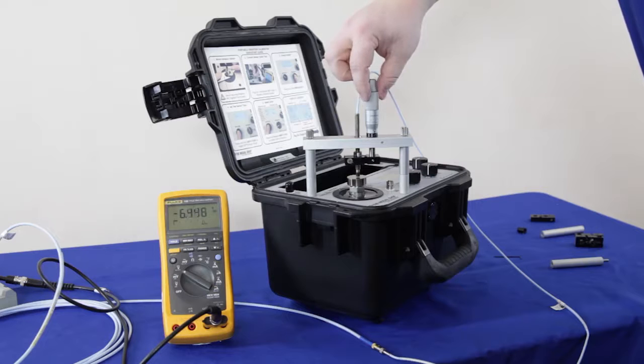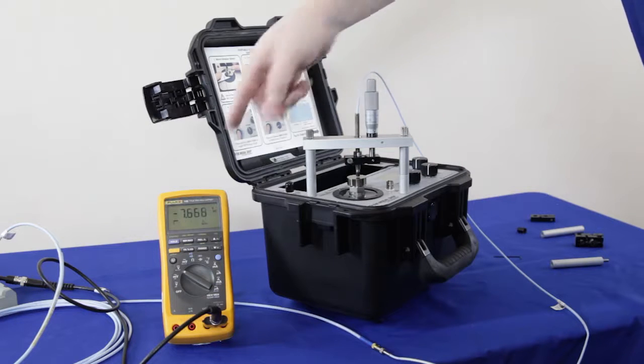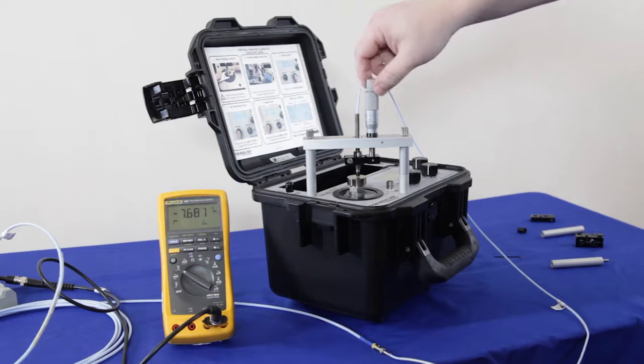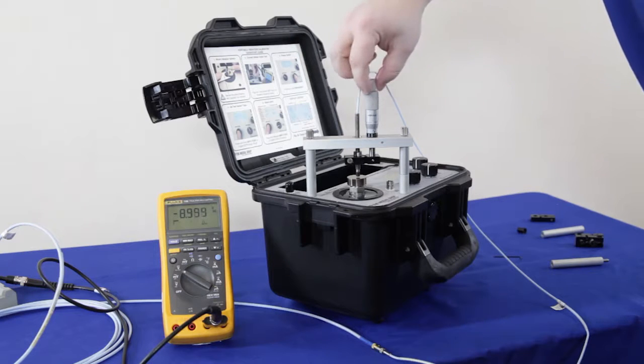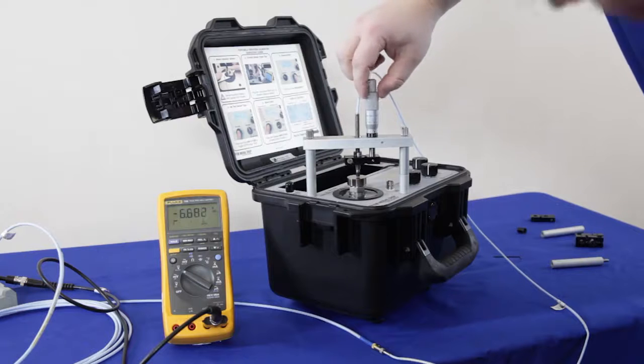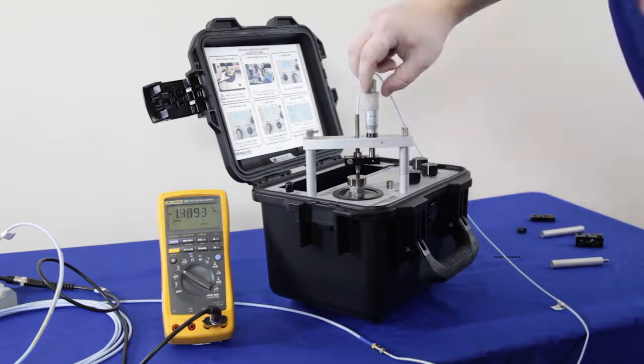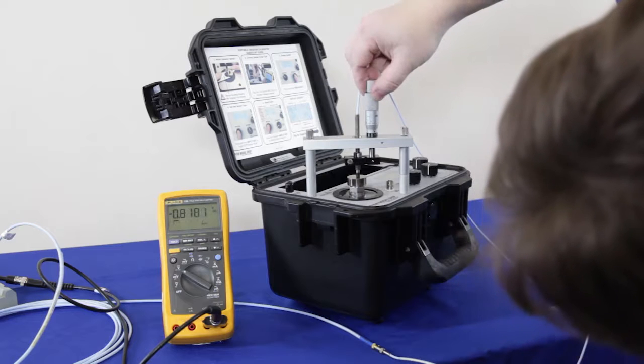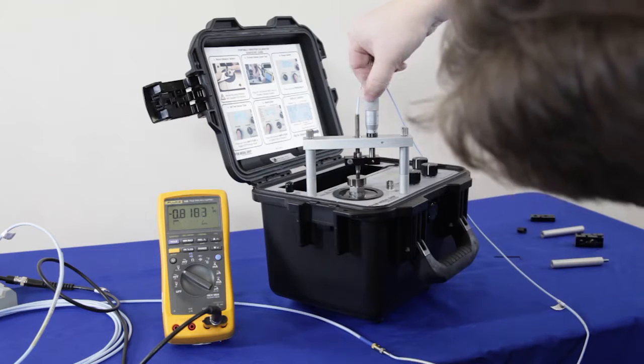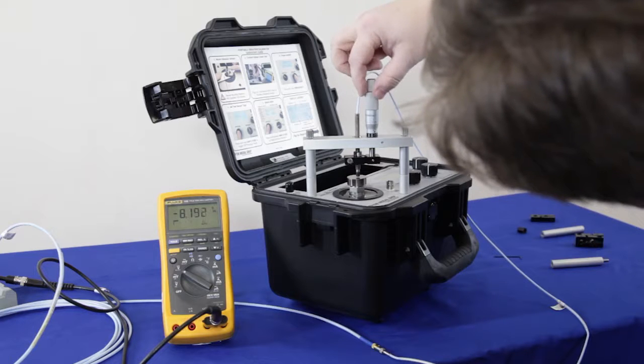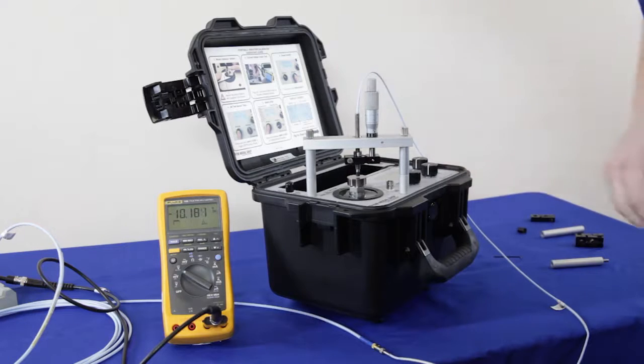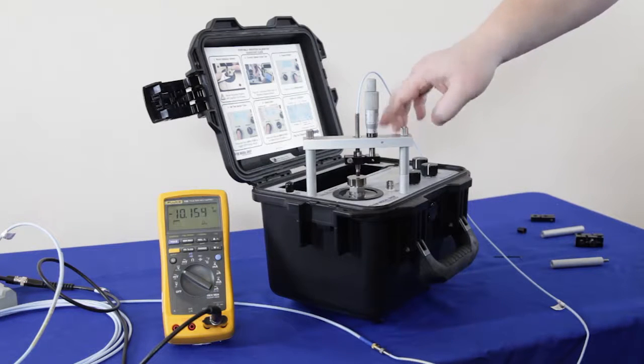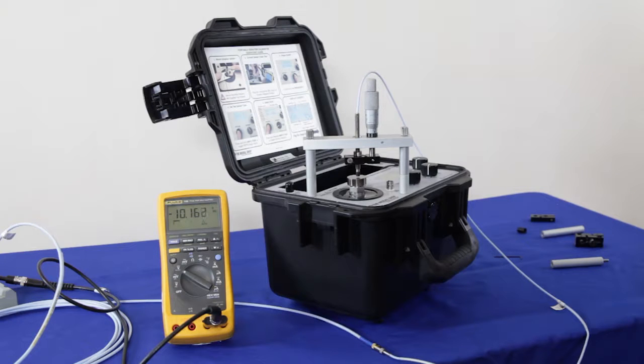Now you're probably also wondering, do you even need the Fluke meter or the voltmeter here? And it turns out not really, because a great way to cheat is to actually visually see where the probe touches the target, and once it's touching, spin the micrometer twice around. Spinning the micrometer twice around is 50 mils, and you can see I got very close to -10 volts just by doing that. So if you don't have a voltmeter, you can always use the micrometer. 2 times around with the micrometer is 50 mils, and that's the correct gap voltage for testing a proximity probe.